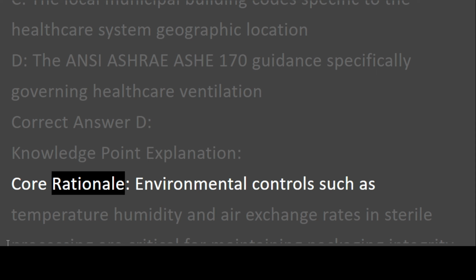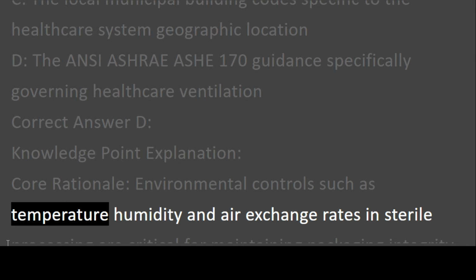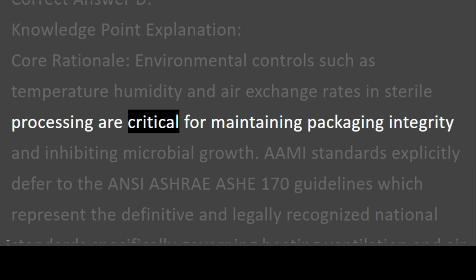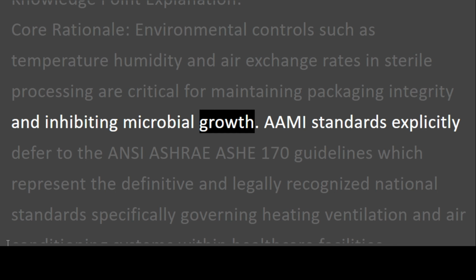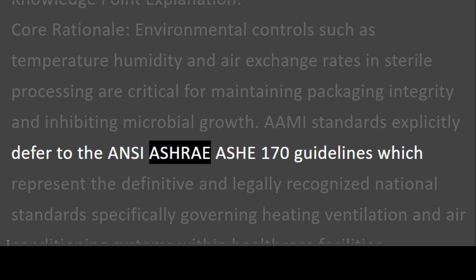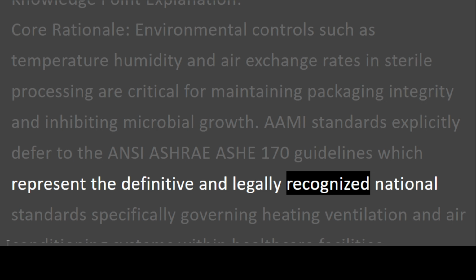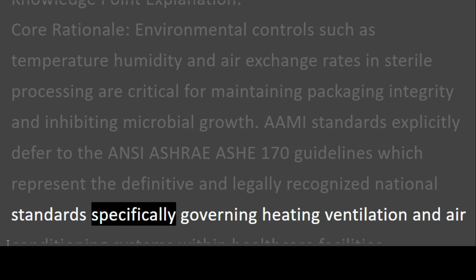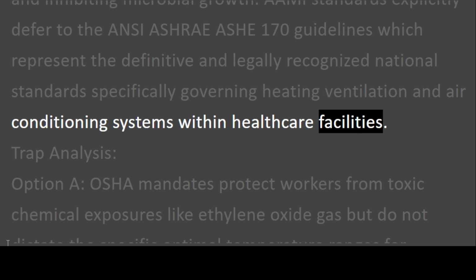Core rationale. Environmental controls such as temperature, humidity, and air exchange rates in sterile processing are critical for maintaining packaging integrity and inhibiting microbial growth. AAMI standards explicitly defer to the ANSI/ASHRAE/ASHE 170 guidelines, which represent the definitive and legally recognized national standards specifically governing heating, ventilation, and air conditioning systems within healthcare facilities.